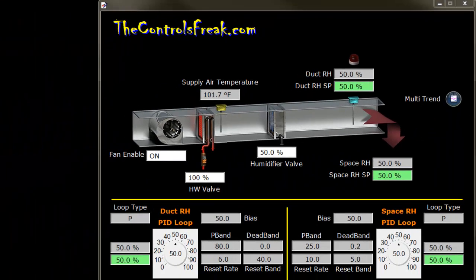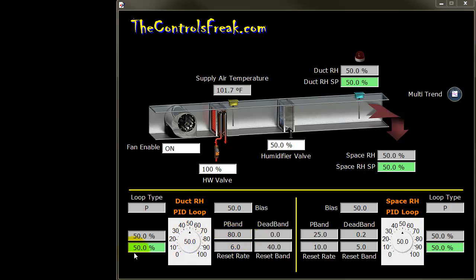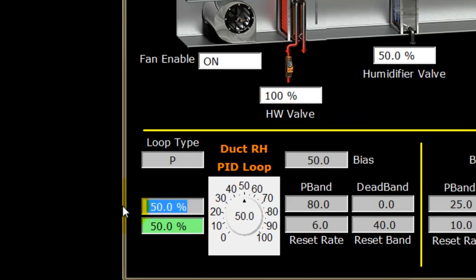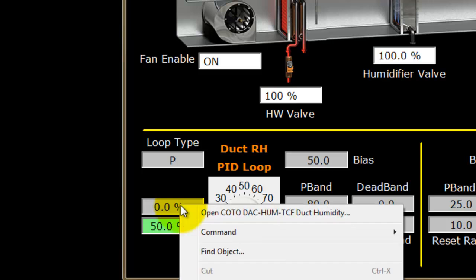Now let's test some things. We're looking at 50% on the input — the duct humidity input and setpoint are both at 50% — so the controller is at 50% to maintain that. Proportional-only means it makes no automatic adjustments on its own. If I change the input to zero, it forces the output to 100% and stays there. The loop only makes one decision: how far am I from setpoint? Give me a percentage. That's all it does.